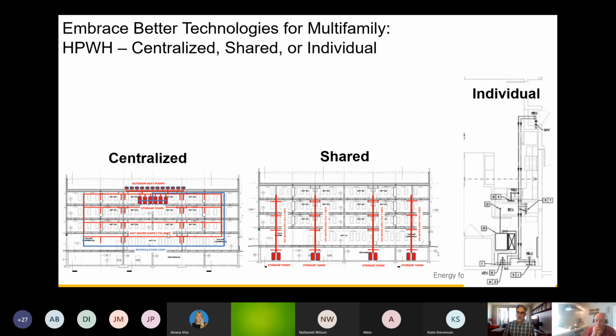The other part is first cost. To run all this copper throughout the building, the plumbers are generally the most expensive trades on site. For them to run all the copper and get the balancing valves correct, so the person at the very end of the run gets the same time to tap as the person closest to the hot water tanks, is nearly impossible. It's very, very hard to do.